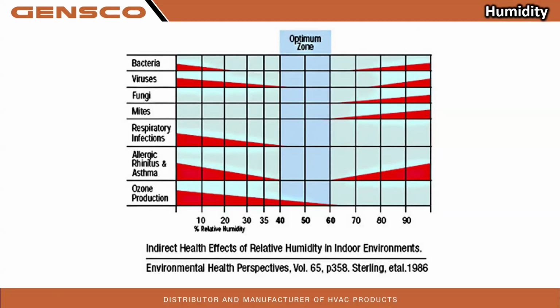And this is outgassing from dying or dead biological material that has been rehydrated by the condensate that's built up in the coil or drain pan. And it can produce an odor that people don't like. Again, it starts around 60% relative humidity, and the higher you are above that number, the faster the growth rate. That's why we want to try to keep the house below that number, so we can avoid having unpleasant things happen. Now, even if we keep the house below that, we can't always keep our unit below that, and we'll explain some of that also.